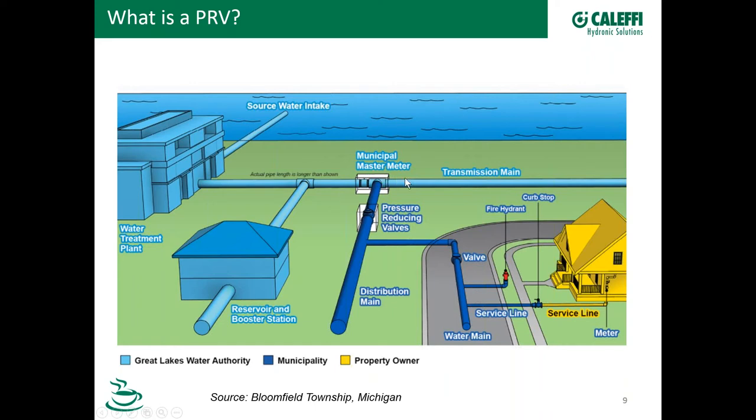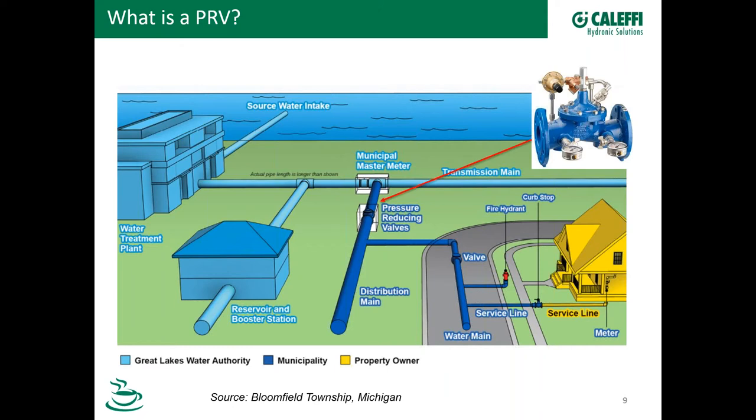From the reservoir, water goes on to a master meter and then the transmission line continues on down. At some point, we come off the transmission line to distribution mains, and here we're showing a PRV in that large pipe. Here's an image of a flanged PRV — this is actually a Caleffi product. The PRV will reduce and stabilize that main supply water pressure to a usable level. Main supplies can be very high in pressure and too variable for the end user, and that's really the base purpose of the PRV.